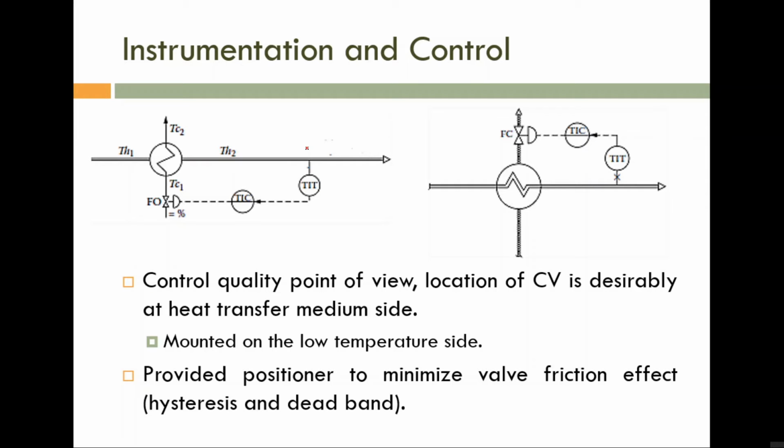Okay. Now, what is the process equation that we are using? Considering this cooler for explanatory purposes, Cp into Wp into (T1 minus T2) is equal to CH, the specific heat of the heat transfer medium, that is the cooling liquid, into WH, the flow rate of the heat transfer medium, into (T4 minus T3). So this is the process equation.